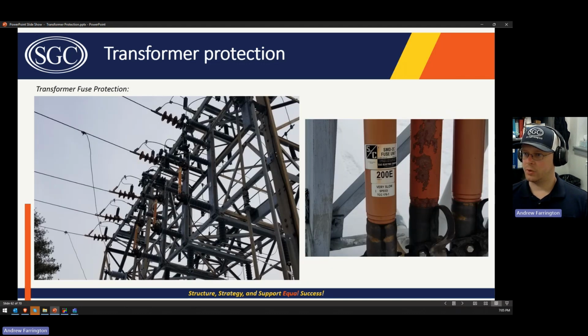metering, SCADA control, event records, things that are often provided with modern microprocessor-based relays that you don't get from a fuse. This is a couple more pictures of a fuse transformer. So these are the high side fuses, and this is a close-up of what you might see for a transformer fuse. These are spares that they had hanging there so that if one blows, they can replace it easily.